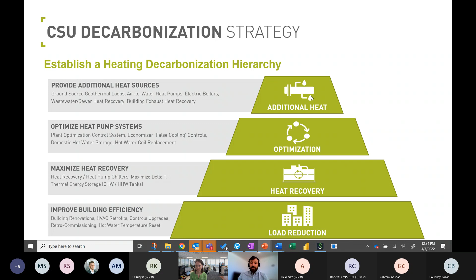I think what's important is we don't need to focus on that 100% immediately. Let's focus on reducing that 60, 70% today, where it's extremely cost effective, and then planning for that last 10 to 30%. And establishing this type of hierarchy on a campus, identifying the specific projects, understanding when can you add a heat recovery chiller or thermal energy storage helps to change the mentality of then, we only need that additional 10 to 30%, not the entire 100.